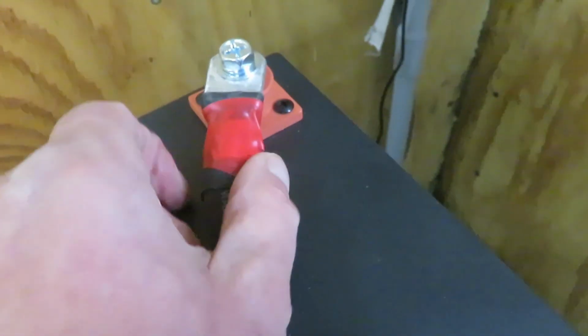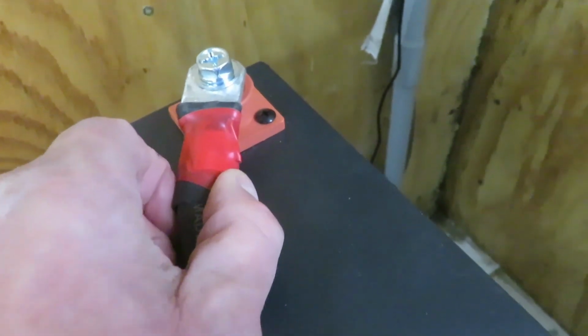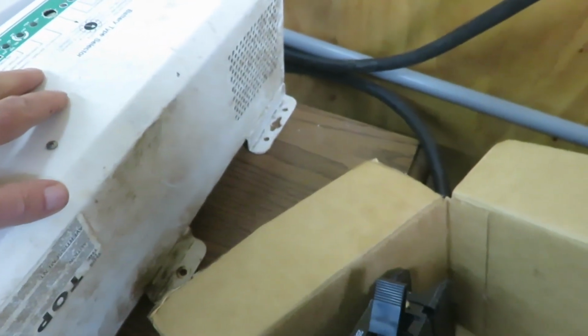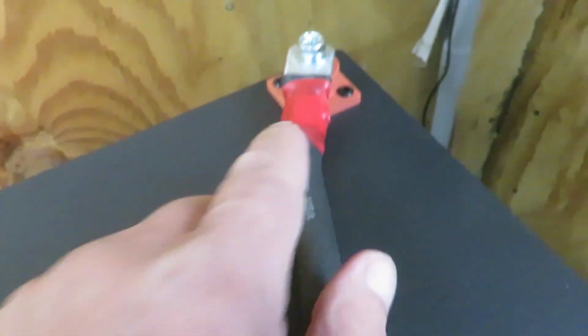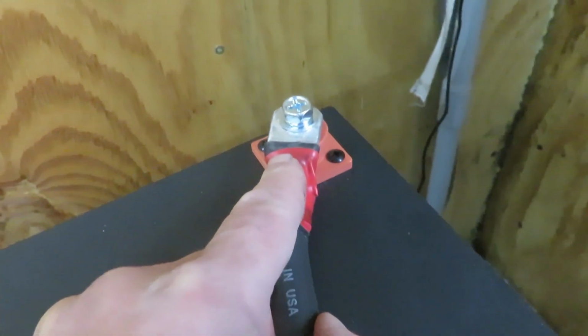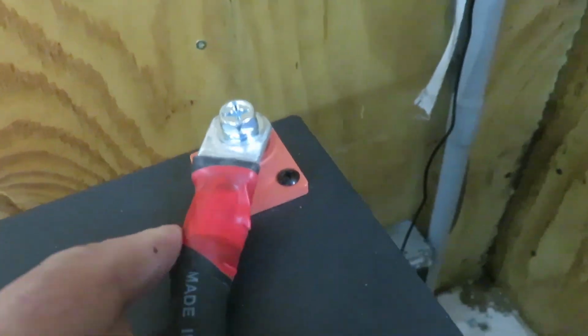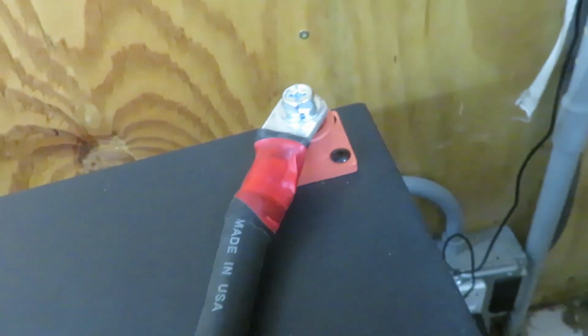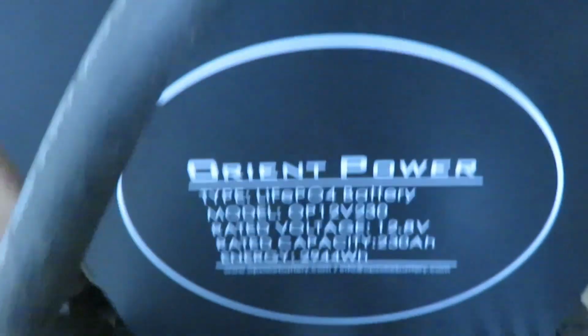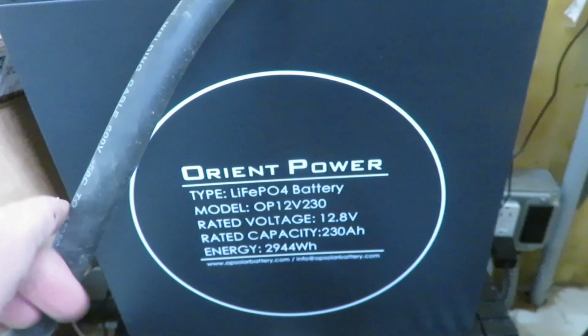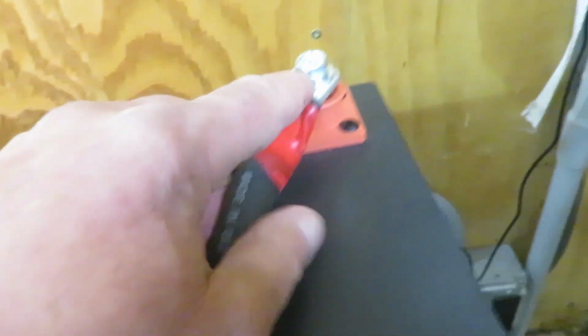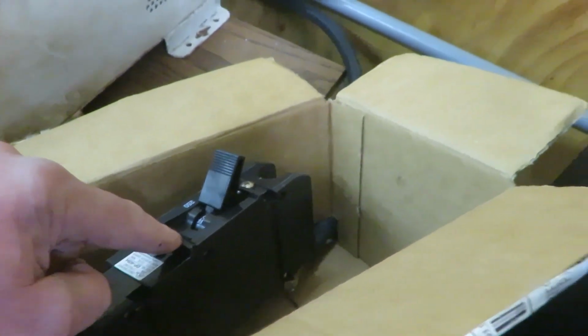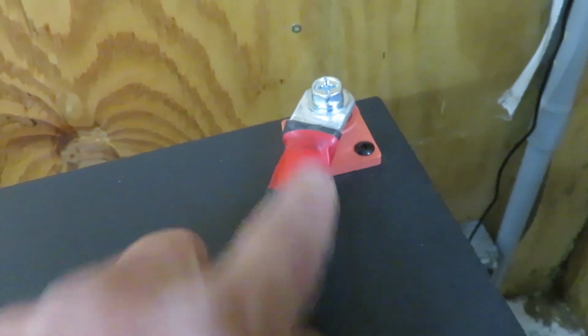If I didn't have the breaker in here, if it was on and I just hooked this up, you might get a huge spark, because if there are capacitors in the inverter, especially a lot of the newer ones, they have big capacitors, and you'd get a huge spark and a loud noise that would scare you pretty bad. You'd think something bad really happened. That's because the capacitors can charge an instantaneous amount of power really quickly, so it's a surge. Better to have the spark here than there when you're hooking it up.